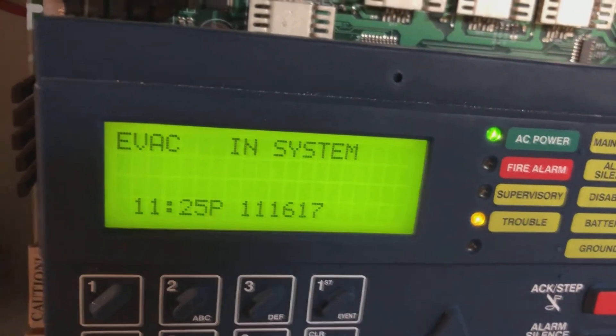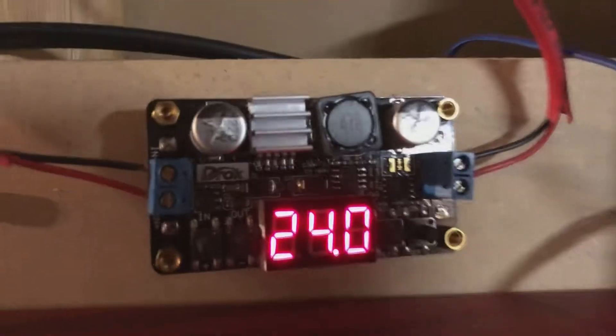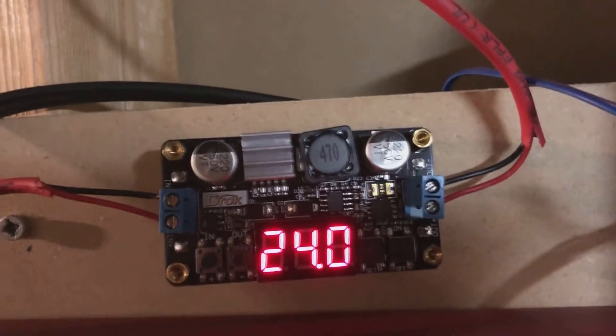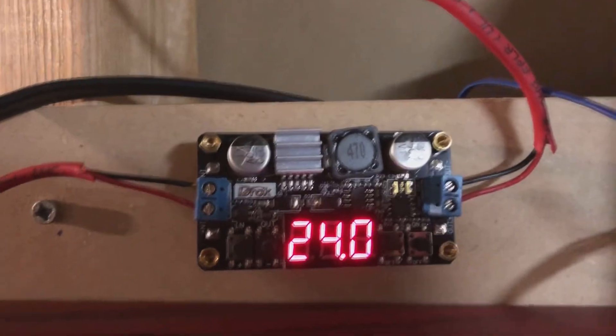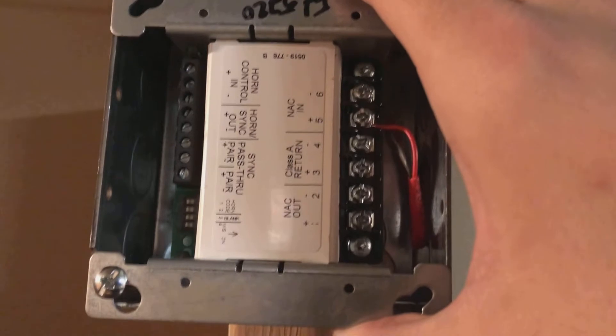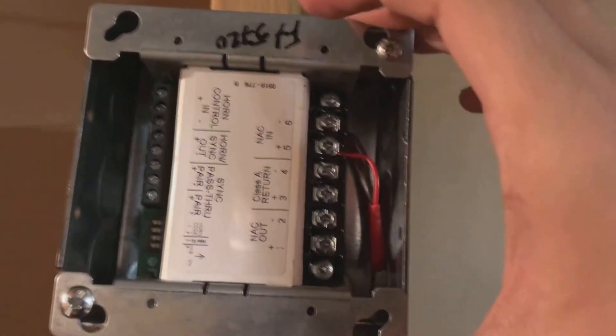And this will eventually go out to the devices - I haven't done that yet but it just goes up into the voltage regulator and then into here. So I'll show you - I'll do a manual back on the system. Now you'll actually hear it clicking here. You'll see it come up to 24 volts - you might see a strobe in the video that is the EST strobe from last week's video. So you've got 24 volts going in here that comes out clean current over here, so this thing is getting some clean current right now - it is absolutely happy about that. So now let's go ahead and get the strobes hooked up on here.